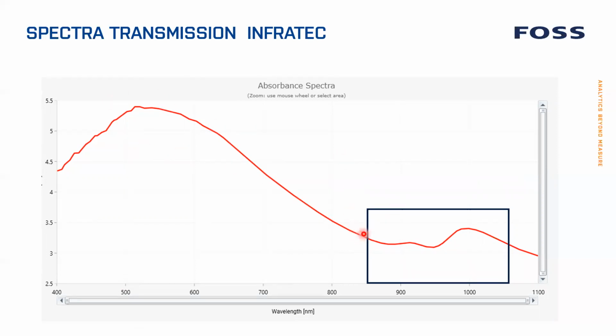Doesn't make a big difference because in Infratecs and FoodScans, we're only using this small range up here between 850 and 1050. And this is how all the spectra look in an Infratec. They have a small peak here and a bigger peak here. And more or less independent of what kind of sample you have, it will look the same. And that's why you need these statistical tools to make calibrations for it, because for the eye, they will look the same, but using statistics, you can actually see the difference.